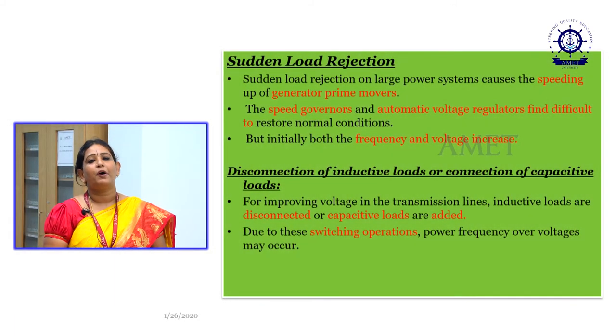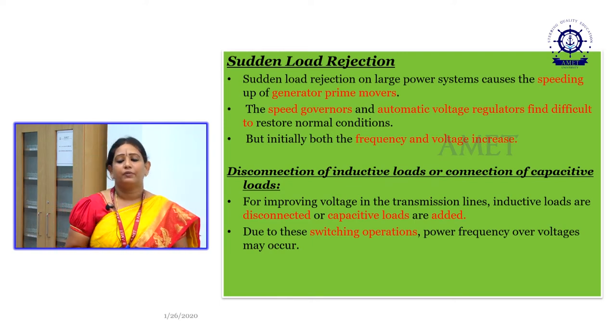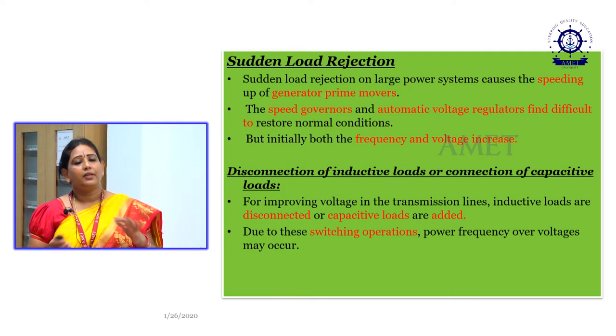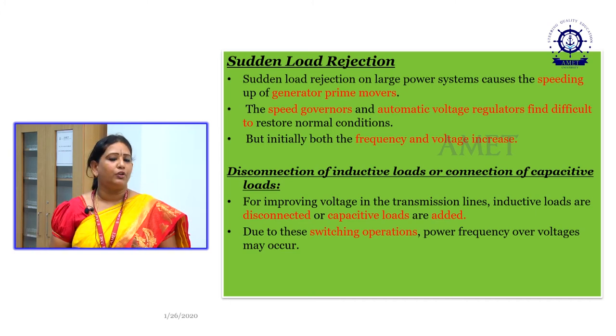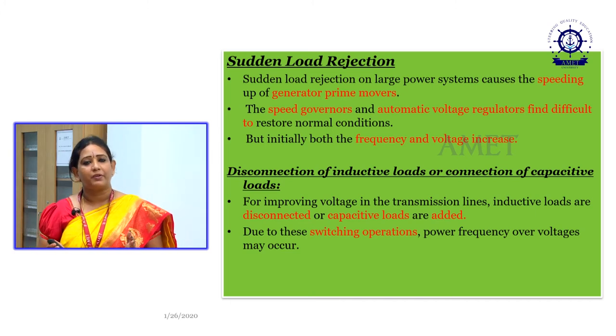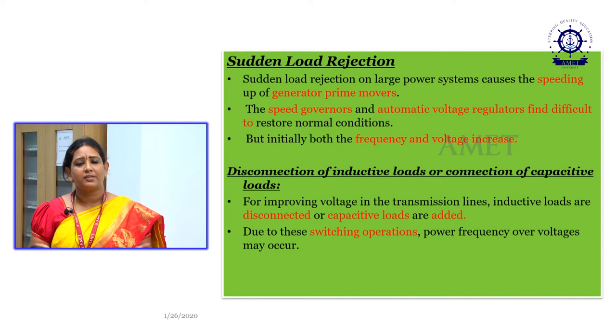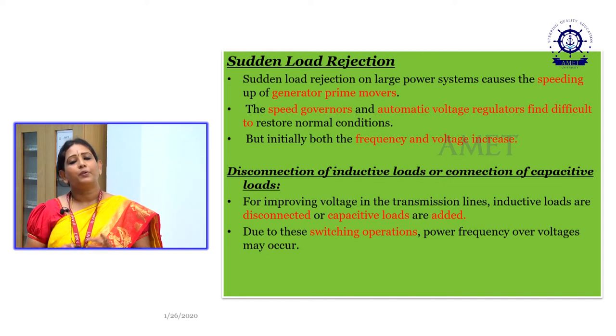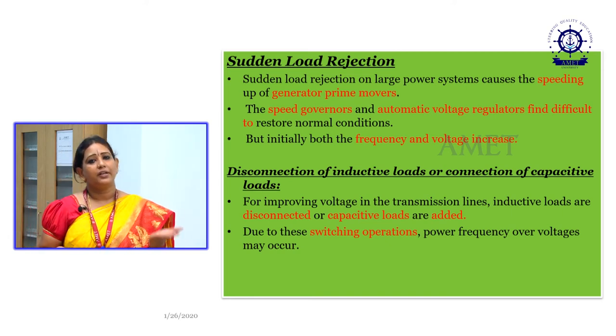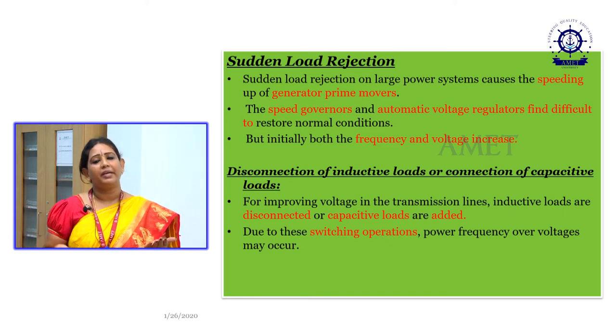And let us see the first causes for power frequency overvoltage. One is the sudden load rejection, as I said previously. We know very well that the entire power system has to work efficiently and effectively. What we as power system engineers have to do is balance the generation and the load. If there is any sudden disconnection or decrease in the load, the generation is affected. So the frequency may increase, and we want to maintain a balance.